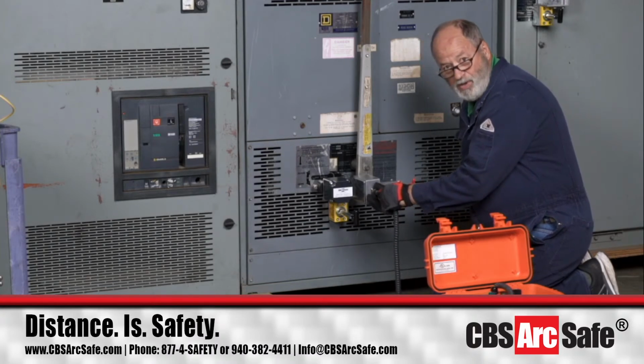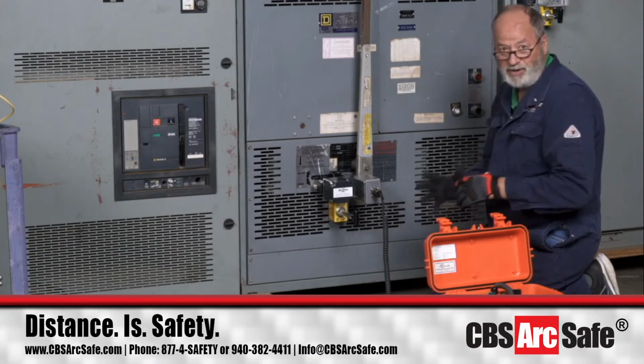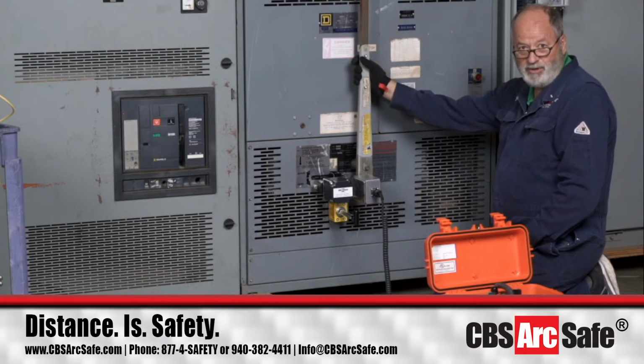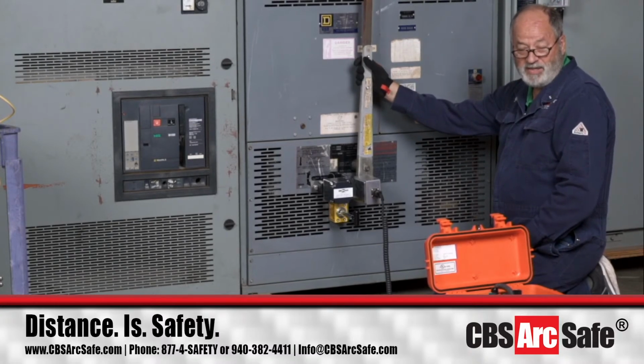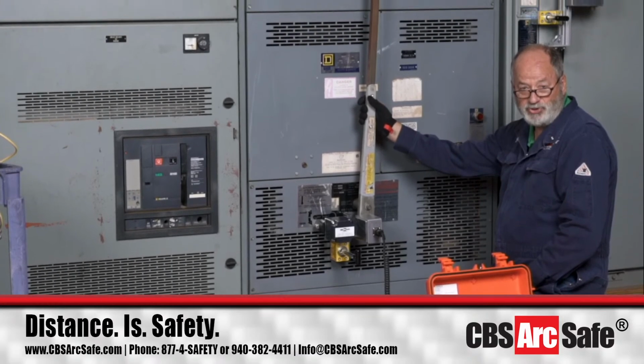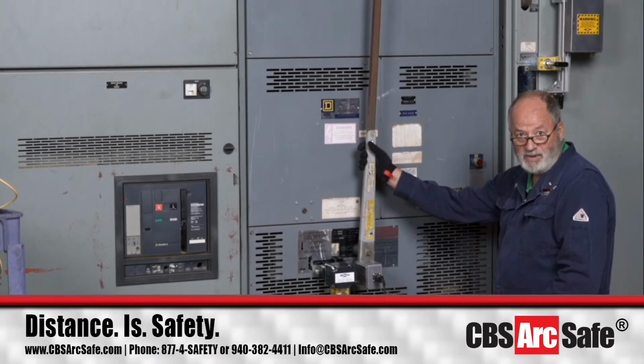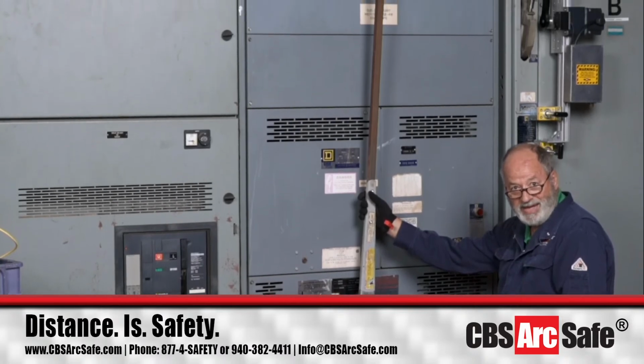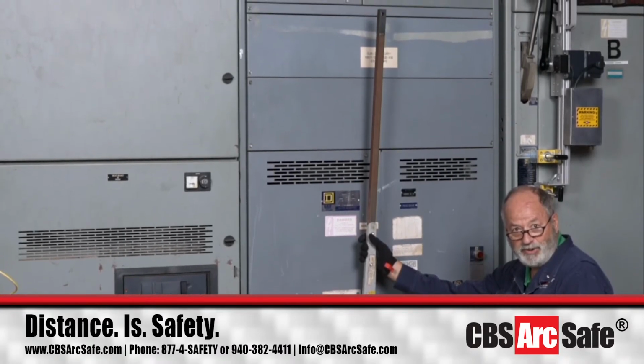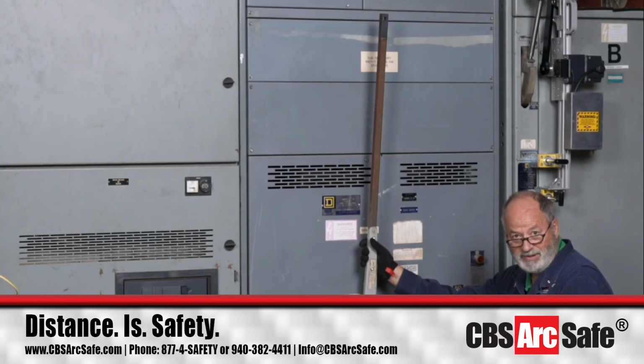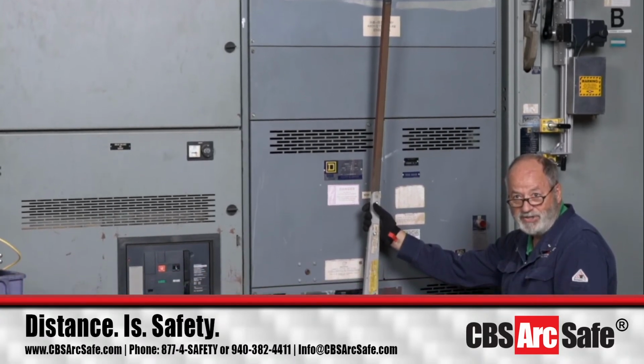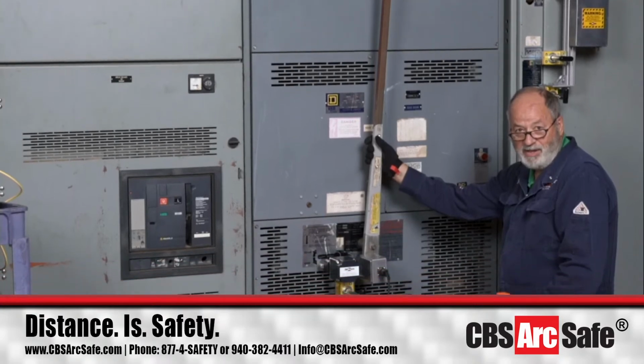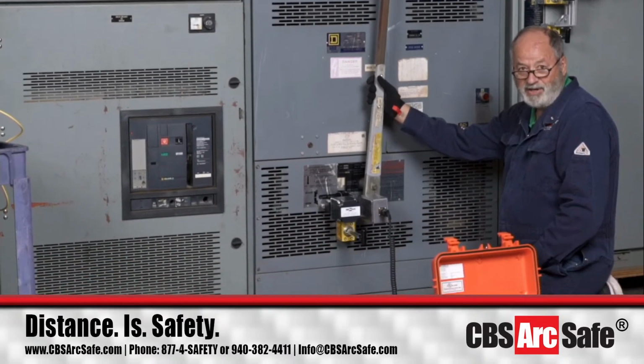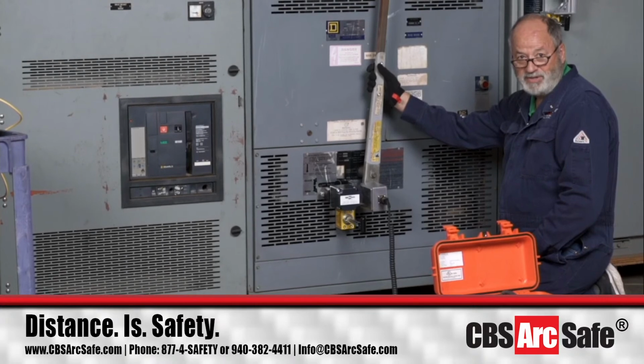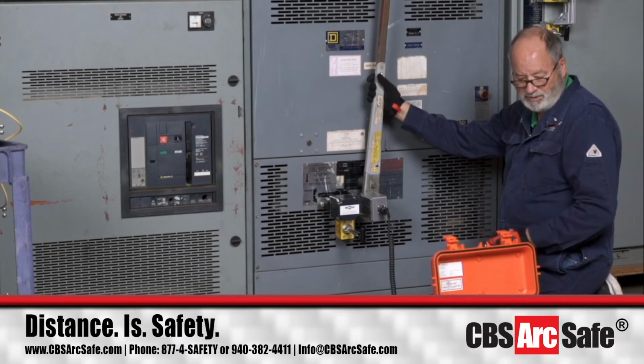One of the funny things is when we introduce new people to sales, whether it's a man or a woman, we normally wouldn't have our cheater bar on here for this. This takes over 200 foot-pounds of force to charge the spring. So we bring our new employees out here to have them gain a perspective of what you in the field have to deal with when you're doing this. We've seen cheater bars in locations to help people be able to get this done, because if you got some 150-pound person, they're not going to be able to charge and close this spring. So they have to put a cheater bar on the end of these to be able to do this.